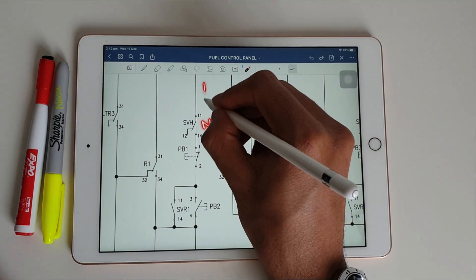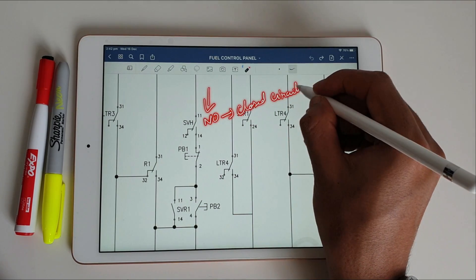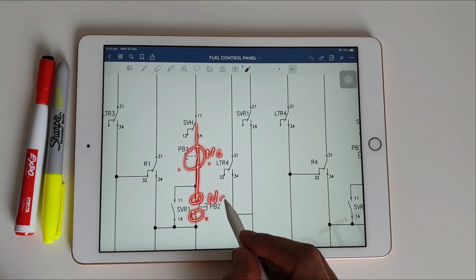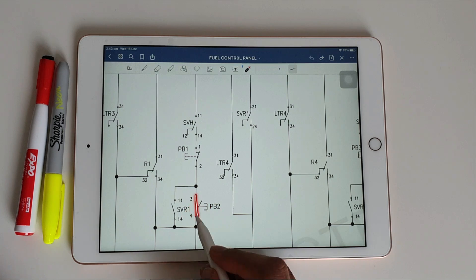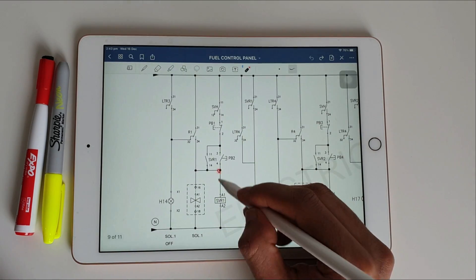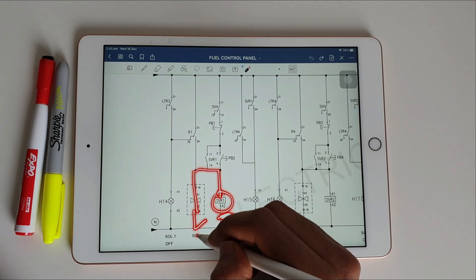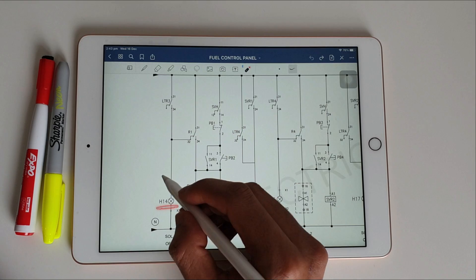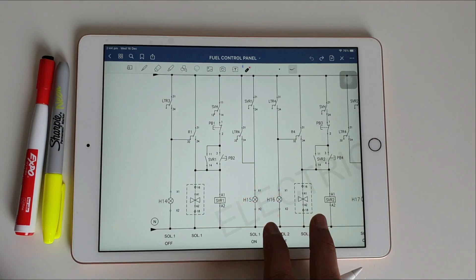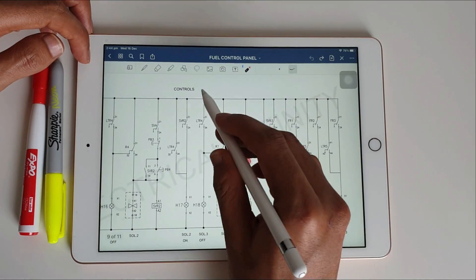For solenoid valve control, the NO becomes NC and with push button one we can turn the panel off, while push button two turns it on. When we press the on push button PB2, the SVR1 relay gets NC and supply passes through the SVR relay A1 terminal, turning on solenoid valve one. On the left side is the indication for solenoid valve off, and on the right side for solenoid valve on. The same setup is used for solenoid valves two and three.